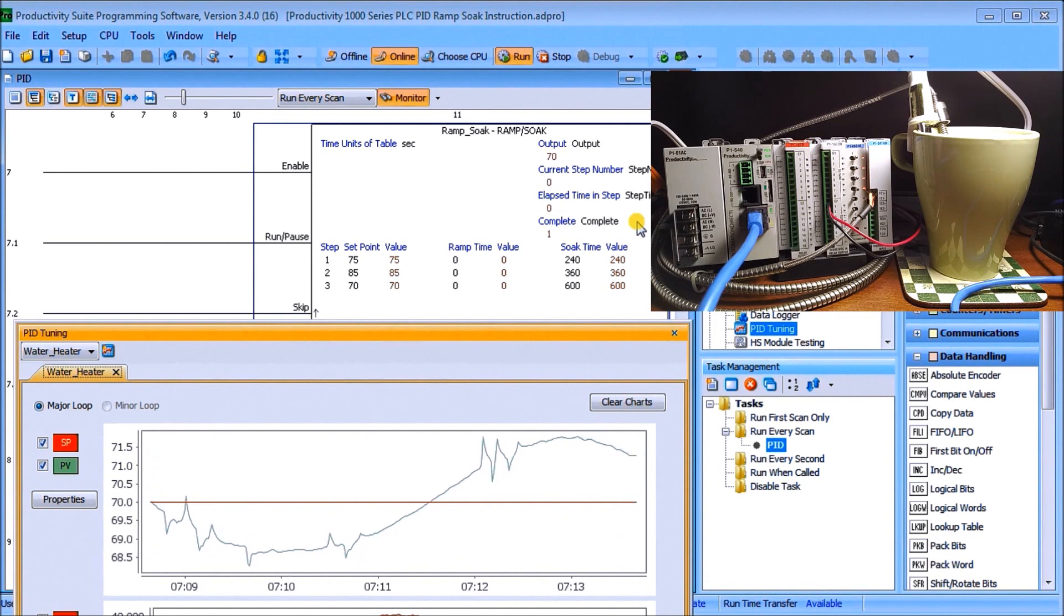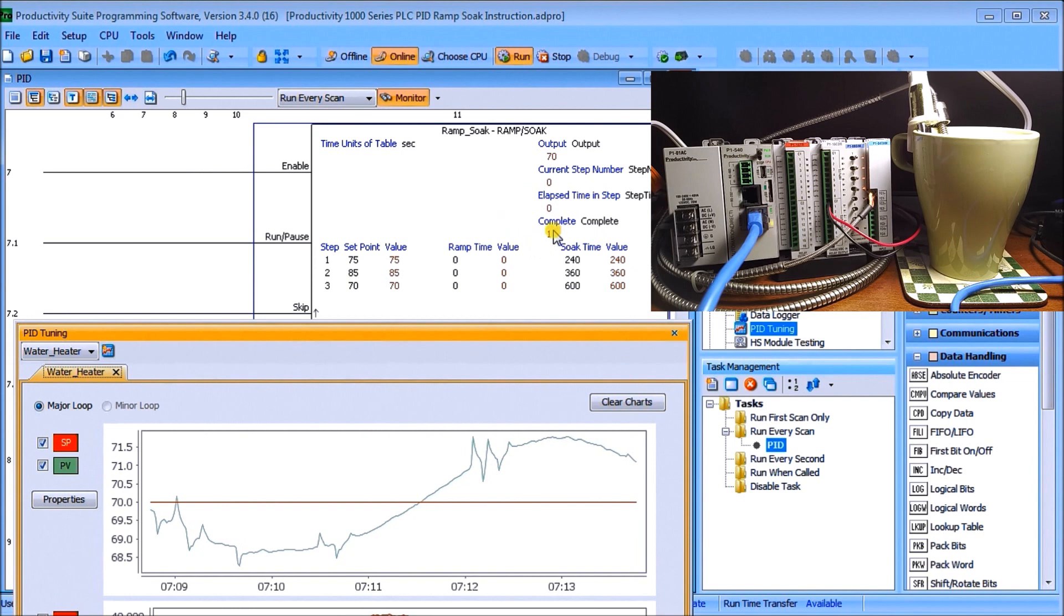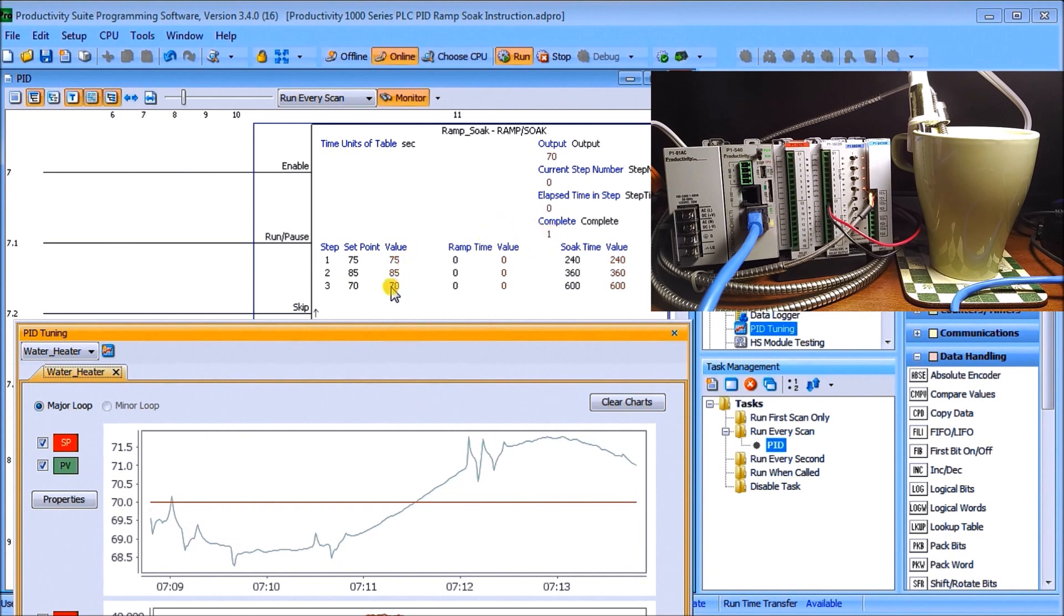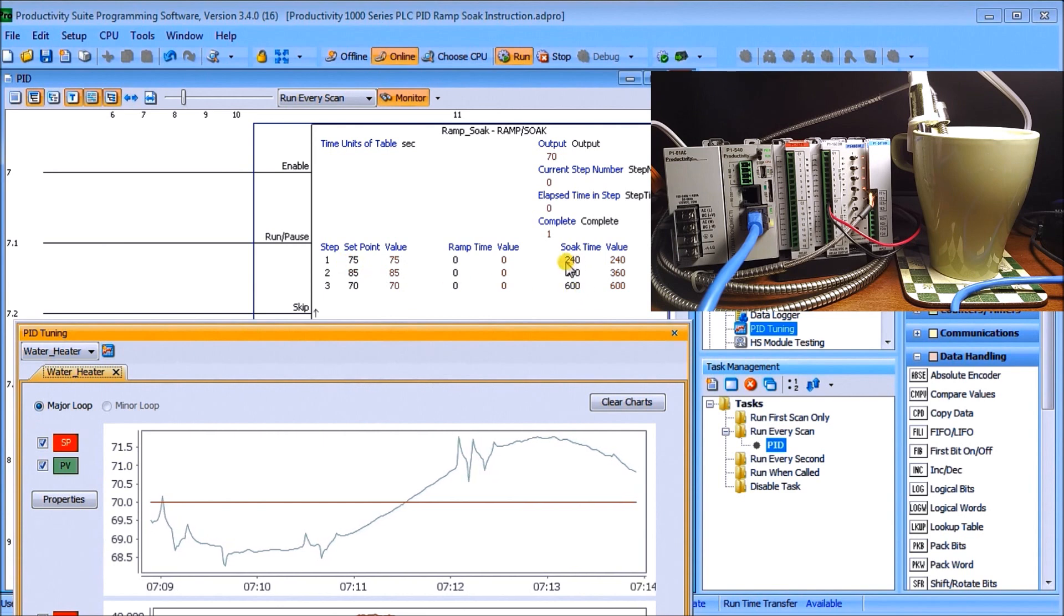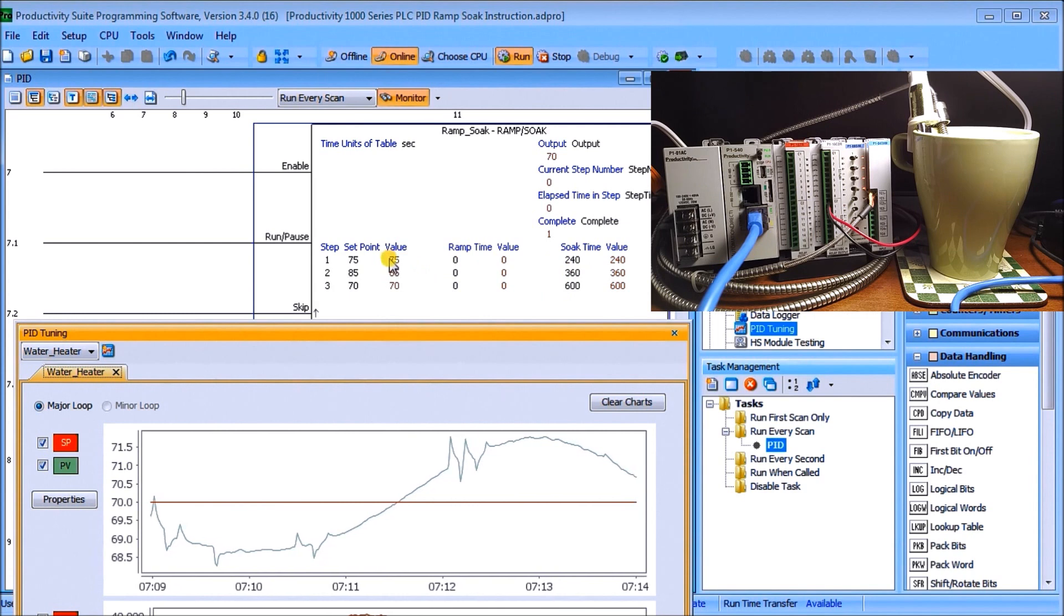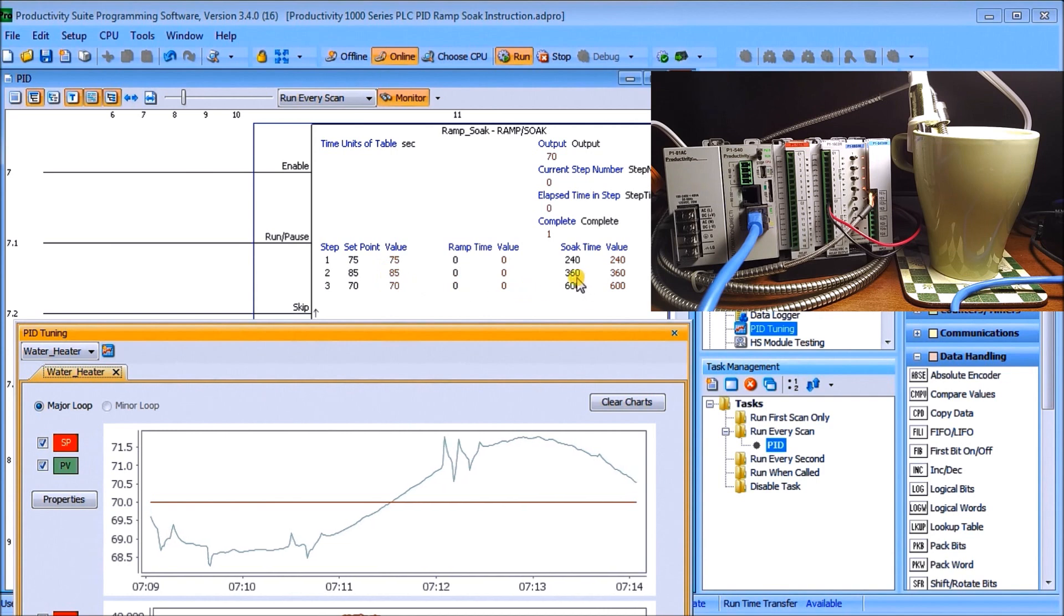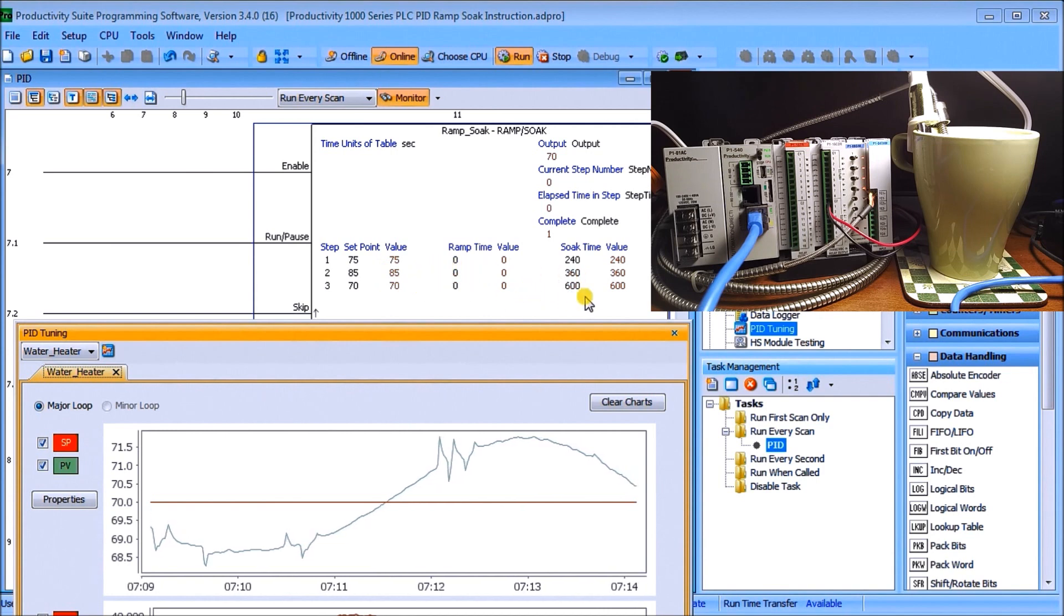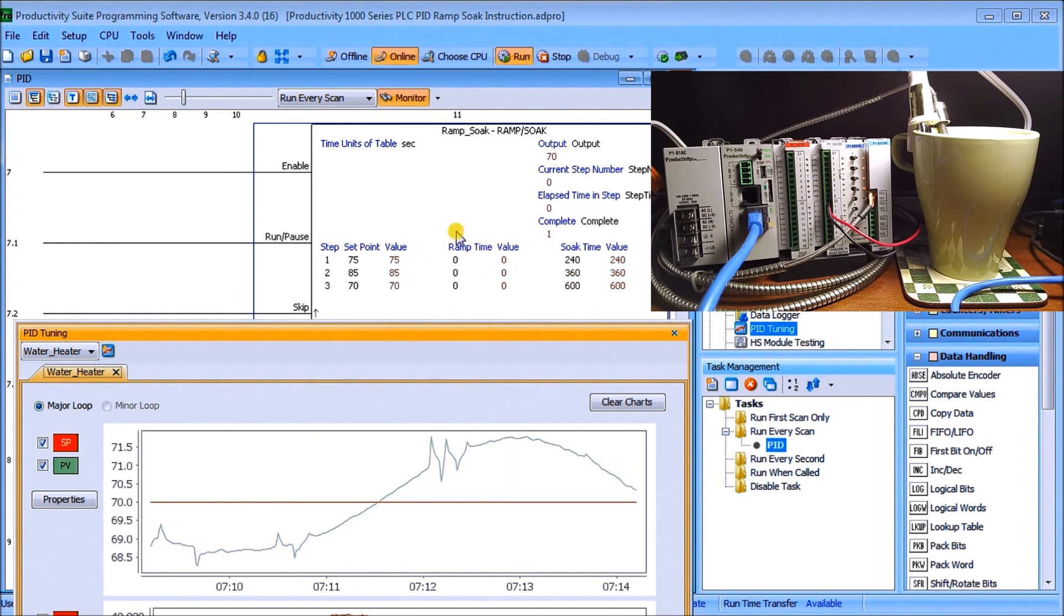So you can see our ramp soak instruction now is complete and we are maintaining the temperature back to 70 degrees. So once again, step one, we moved up to 75 and we stayed there for 240 seconds or as we ramped up, we took 240 seconds then to change it to 85, stayed there for 360 seconds and then we dropped it back to 70. So we went back down to 70 and waited 10 minutes or 600 seconds to go back down again.